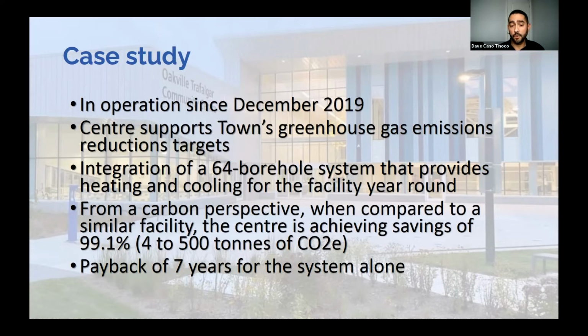Working collaboratively with OEC and Geosource, we integrated a 64 borehole system with heat pumps that could provide the entire heating and cooling needs of the facility year-round. The facility does have 2 large water heaters, natural gas fired, that complement domestic hot water usage. They also have the ability to supplement temperatures in the geo-exchange loop if the ground system isn't supplying enough energy for heating. However, these 2 water heaters are only for auxiliary purposes and do not consume a large amount of natural gas annually.